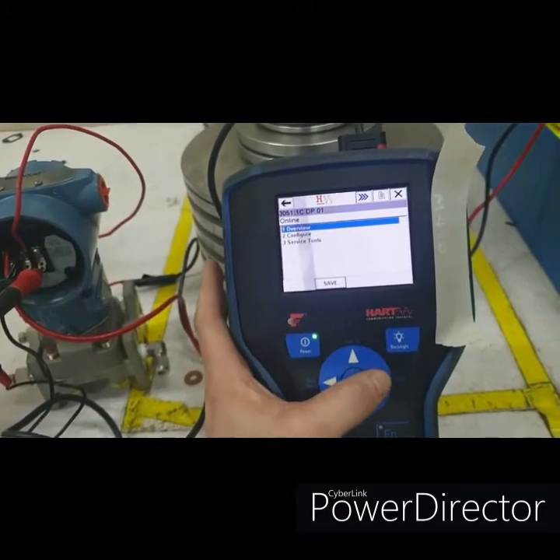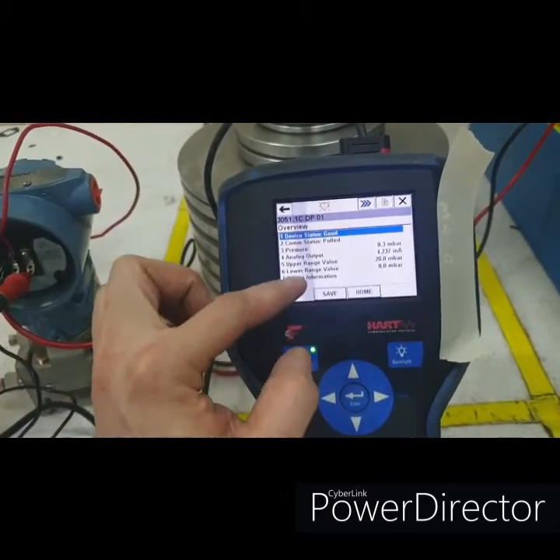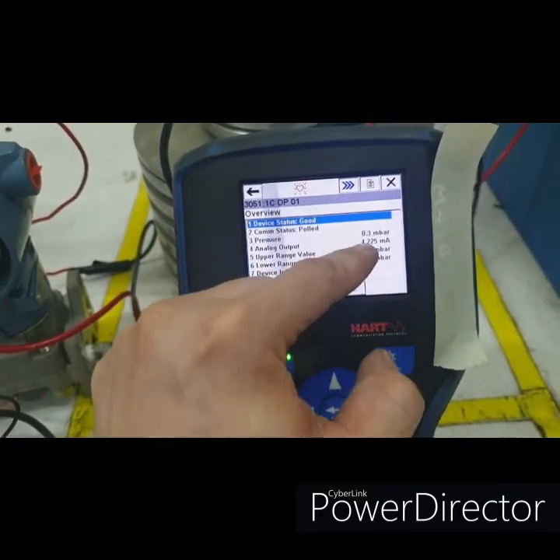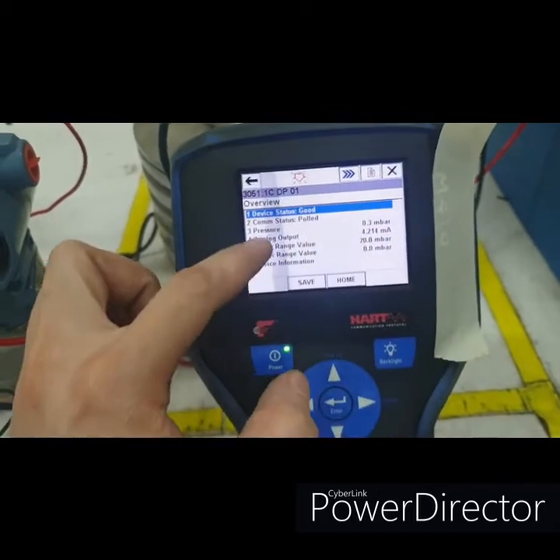So it has changed. The lower range value is changed to zero and upper range to 20, and the pressure is 0.3 millibar. Analog output is 4.22. We can confirm it in the meter also.